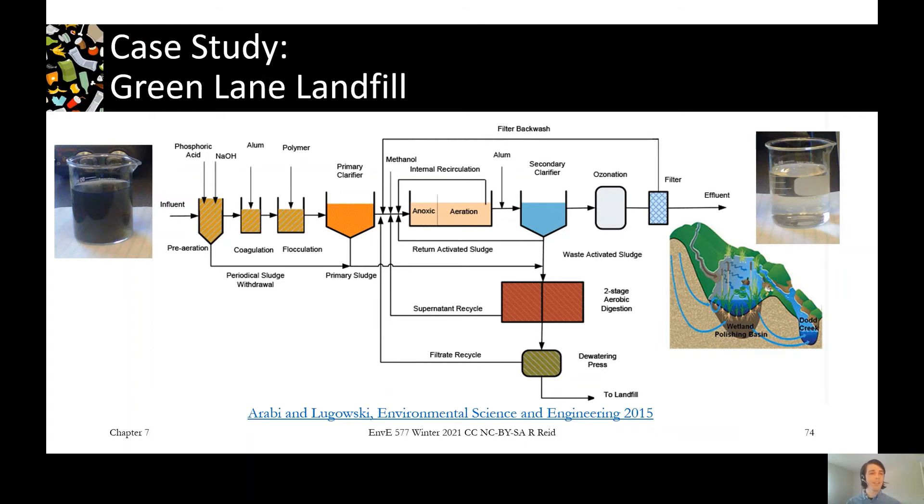And then we've got a coagulation flocculation process. So in a lot of domestic wastewater treatment plants, we go directly into the primary clarifier because we've got a lot of solids. Here we've got some more suspended solids that we want to address right off the bat. So we've got some coagulation flocculation to enhance that.